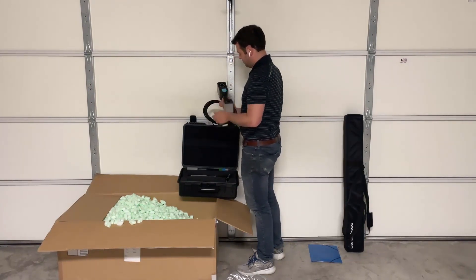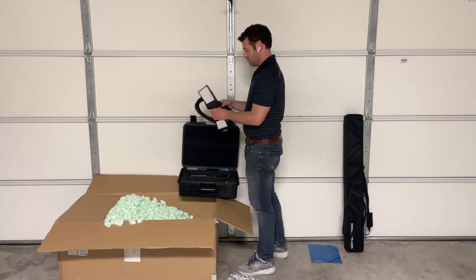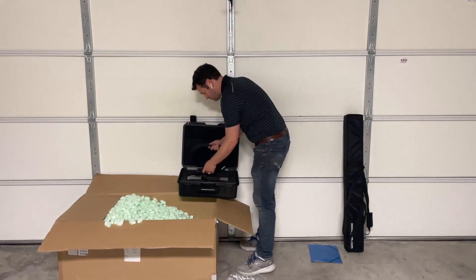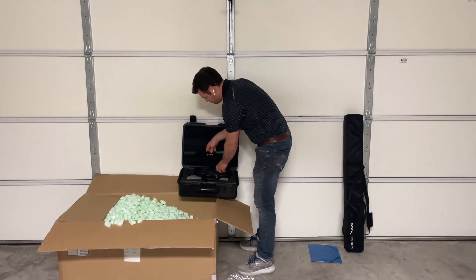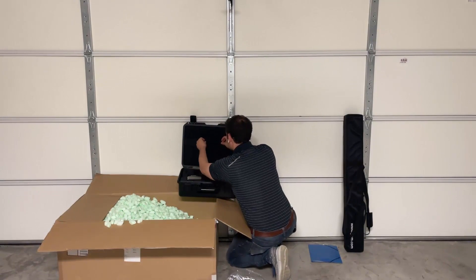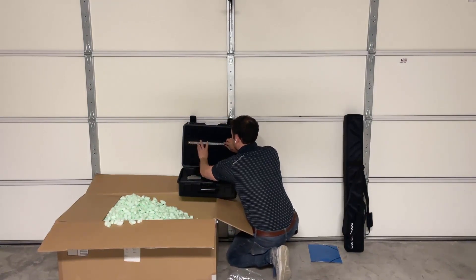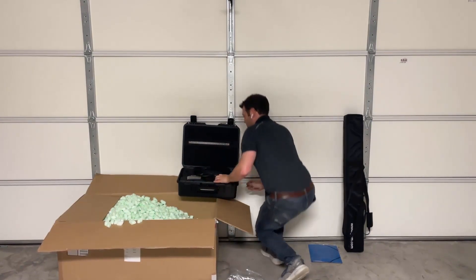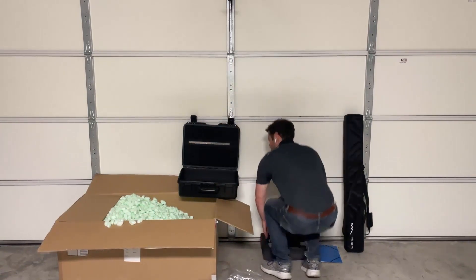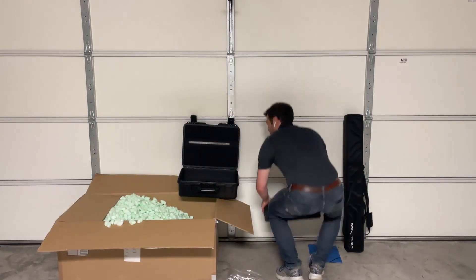So I took a quick look at the scanner — it's a really nice piece of construction. It has the main cord already attached. I decided to pull it out and take a look before continuing with pulling out all the other stuff we had ordered with it. I also took a moment to install the smaller quick calibration scale bar into the foam on the lid of the case. This will be used for a quick calibration; for the full calibration, you'll see later in this video I'll be using the calibration board, which is under the foam insert in the case.